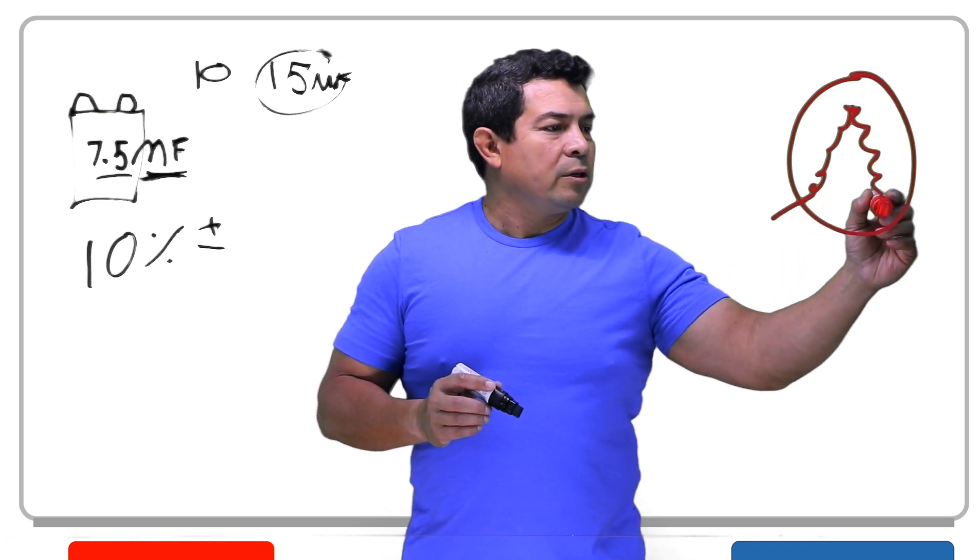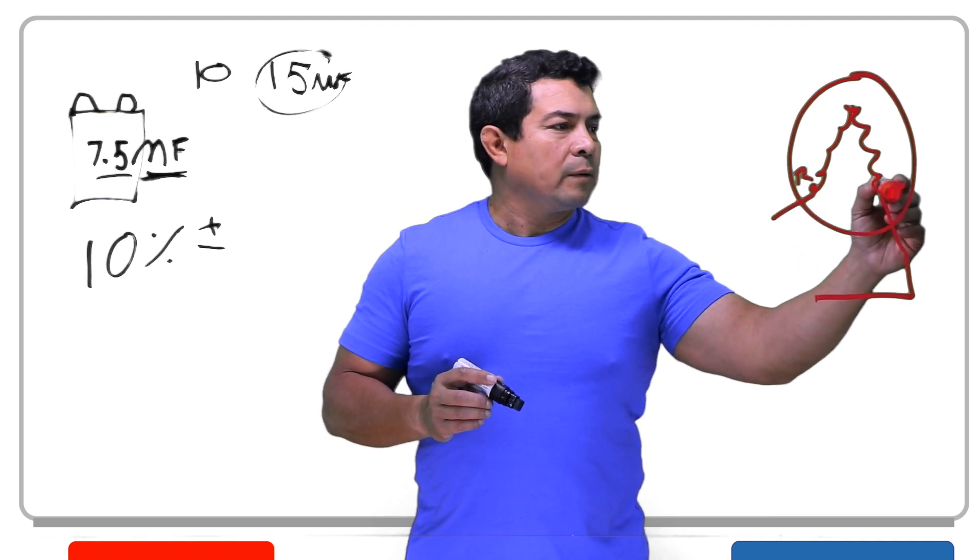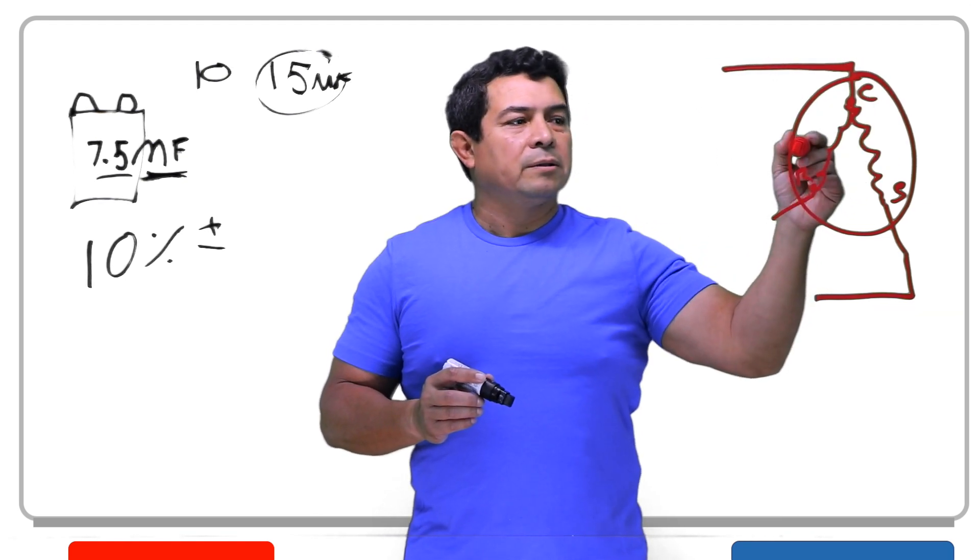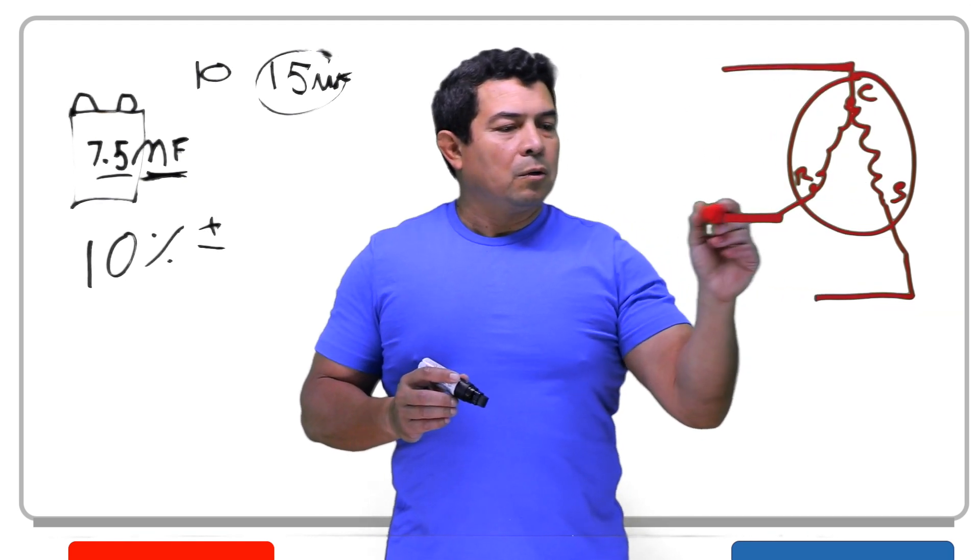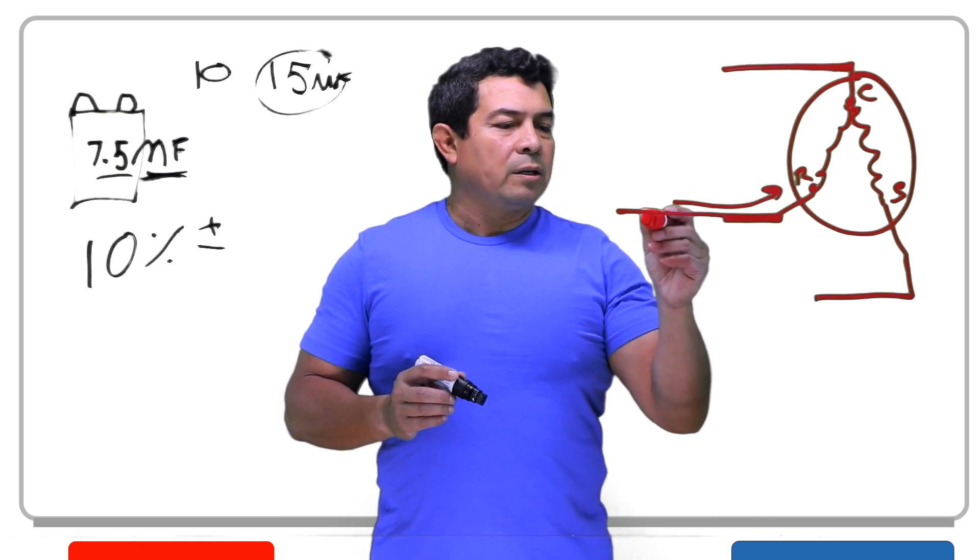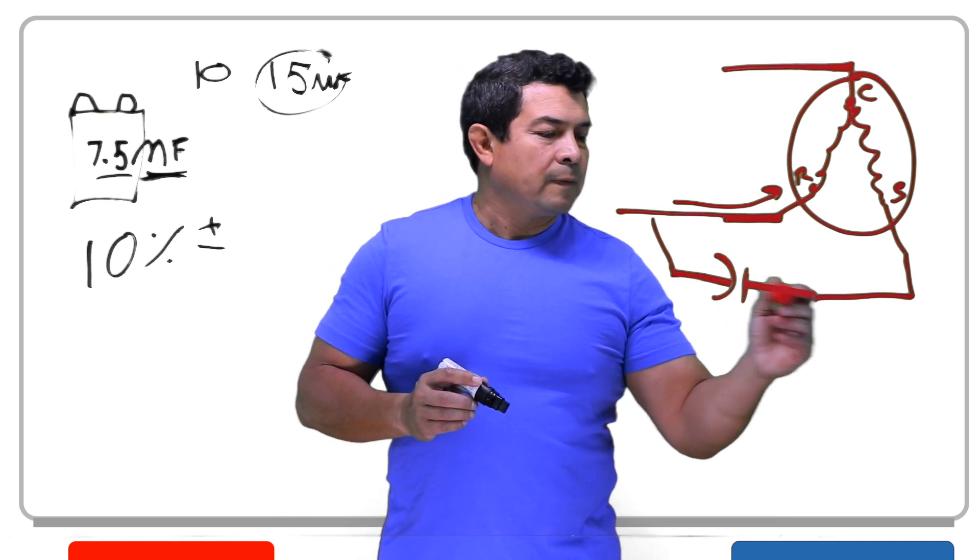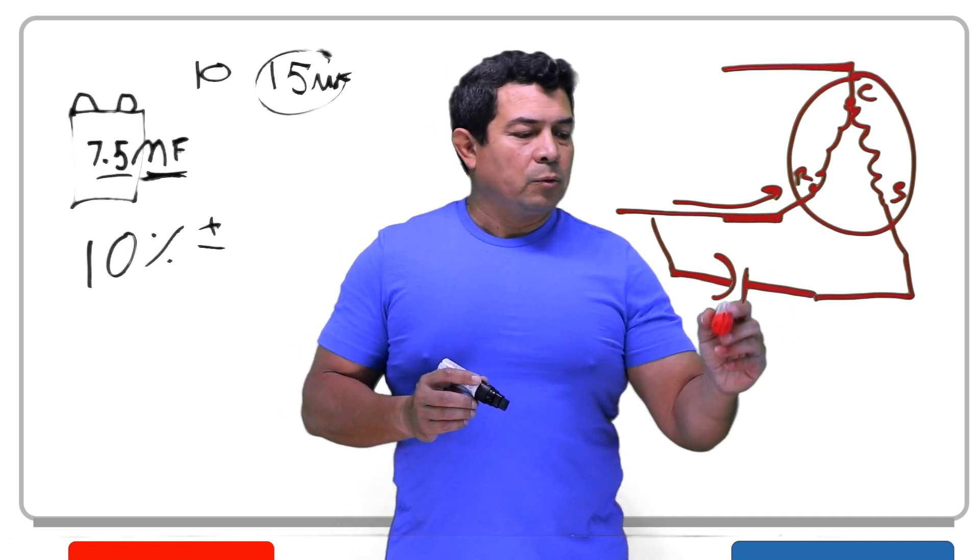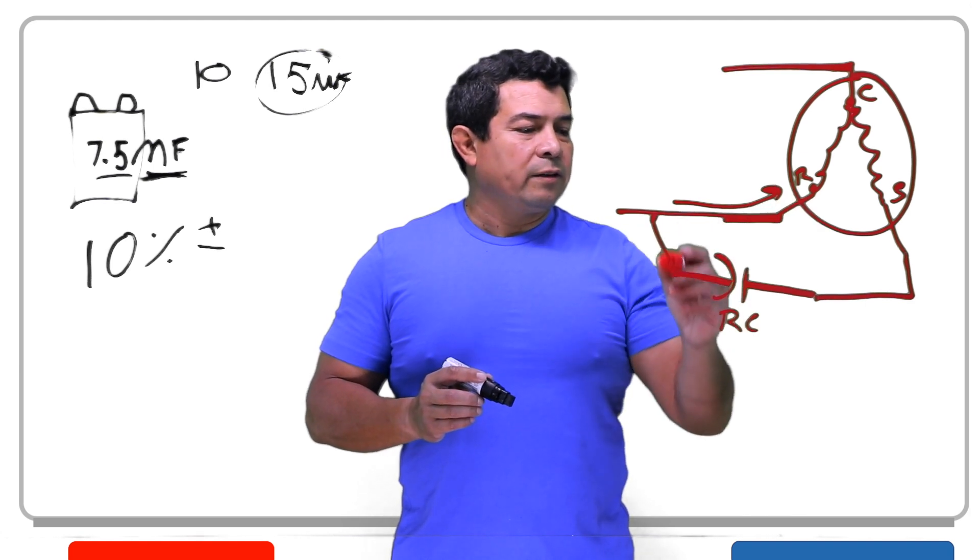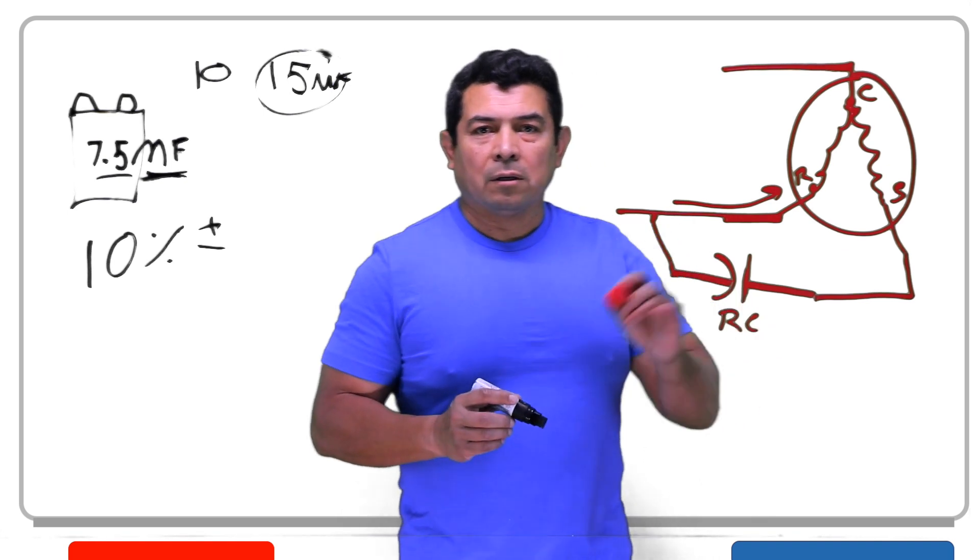Now we have in a single phase motor, we have the two windings like this. One is going to be the run winding. The other one is going to be start winding. You're going to have three connections. This one here is going to be your common. So what I always tell the guys in class is the same line that feeds the run winding always has to feed the capacitor. And this is the symbol for capacitor. This would be your run capacitor. So the same line that feeds the run winding feeds the capacitor, and the capacitor always feeds the start winding, always.